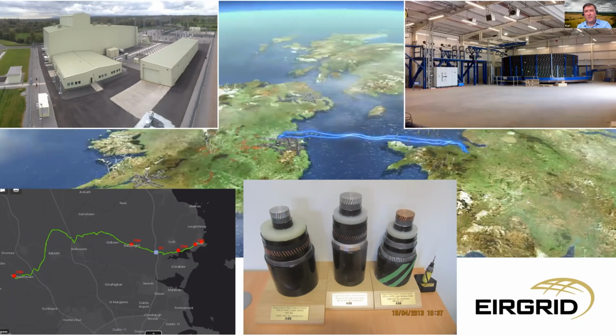The repair preparedness facility is strategically located in a secure deep water port in Liverpool, just around there. And this allows for quick mobilization of offshore repair in the event of a cable fault. In the picture, you can see 10 kilometers of marine cable spare on a carousel in a controlled environment, and routine maintenance consists of ensuring that the mechanical devices remain operational and the asset is secure.